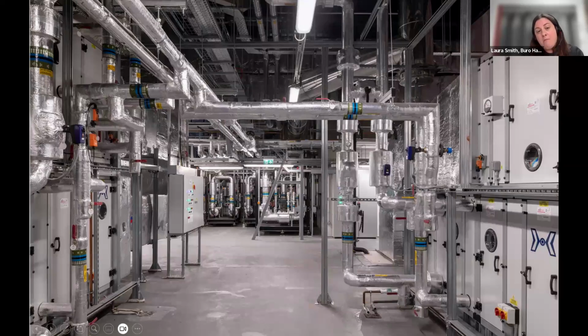Next time you enter a plant room like this one, an air handling unit plant room with some ventilation, a lot of you will probably just see a lot of space in the middle and a bit of equipment on the sides. But really, there's space here for maintenance, so we can pull things out easily from each piece of equipment. There's flexibility to expand and grow, whether an office becomes a meeting room needing more air per person, whether the climate changes and we need more cooling, or whether we're maximizing efficiency through getting the right size of equipment and nice straight pipework runs, with the ability to swap and change things without disrupting the wider systems and building.